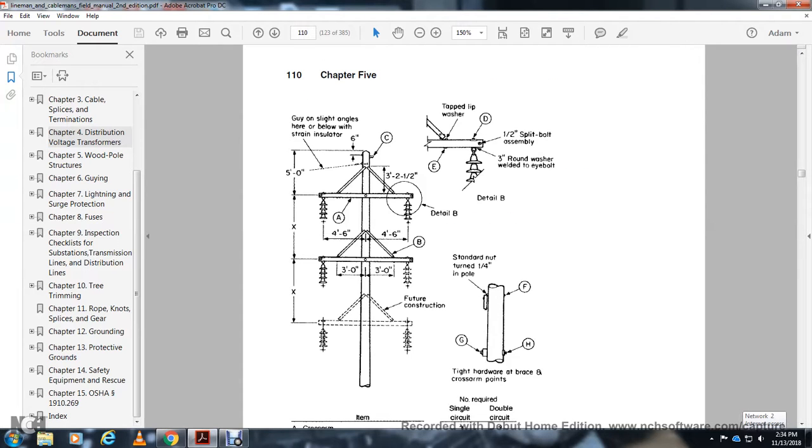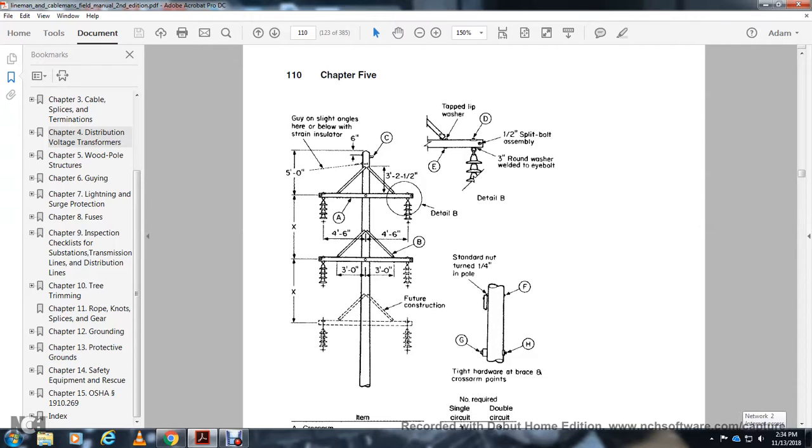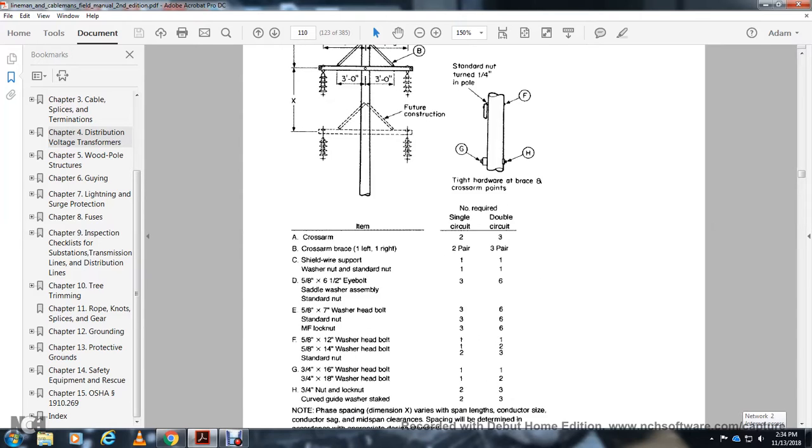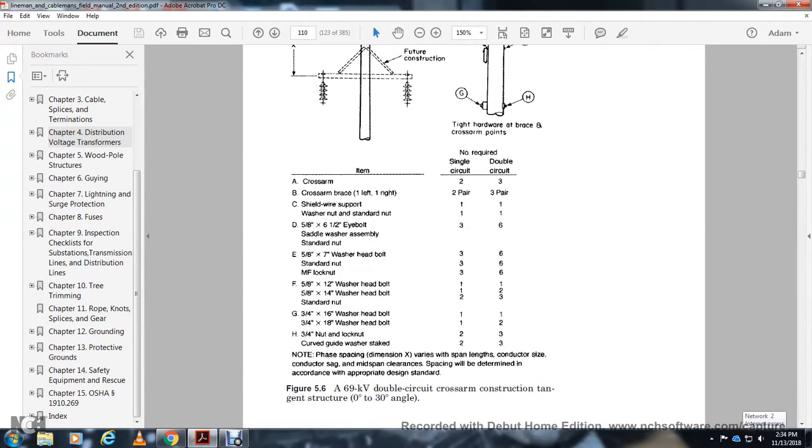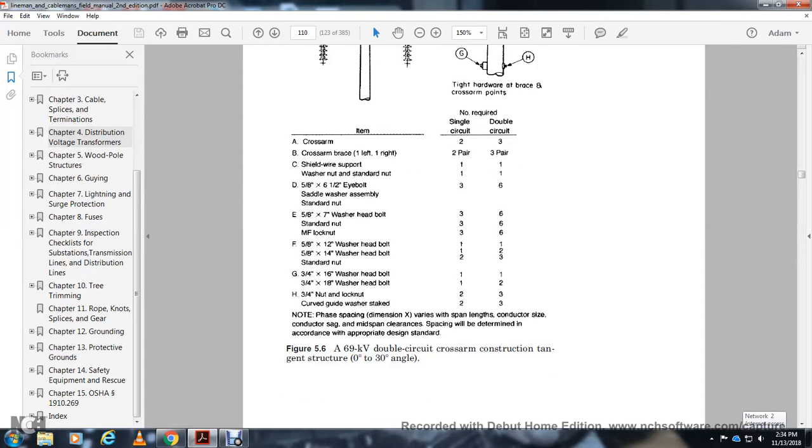Guy and strut site angle details showing hardware, placing cross arms, tap washer, split bolt assembly, round washer, and welded bolt. The 69 kV double circuit cross arm construction for 0 to 30-degree angle structures.